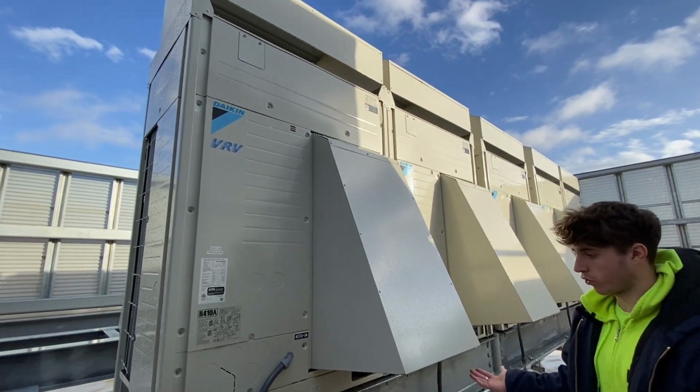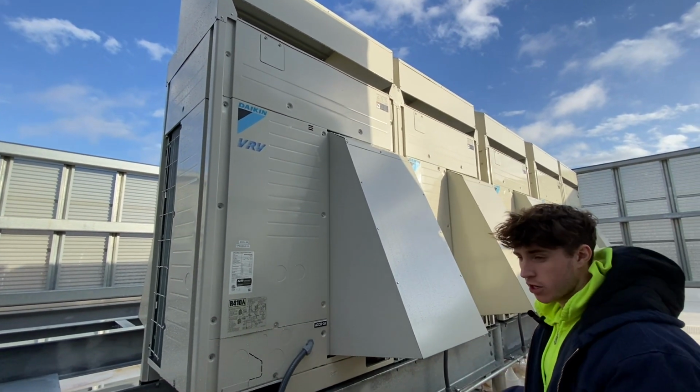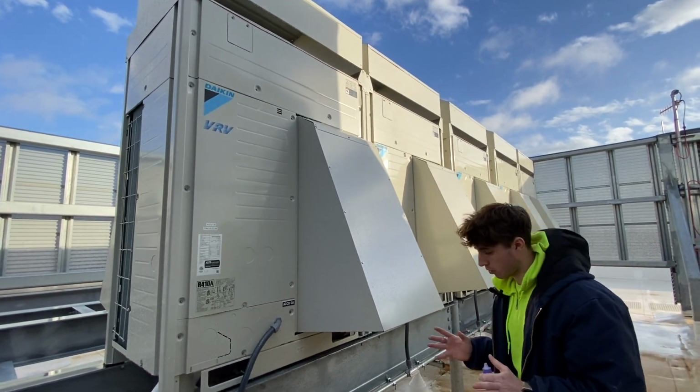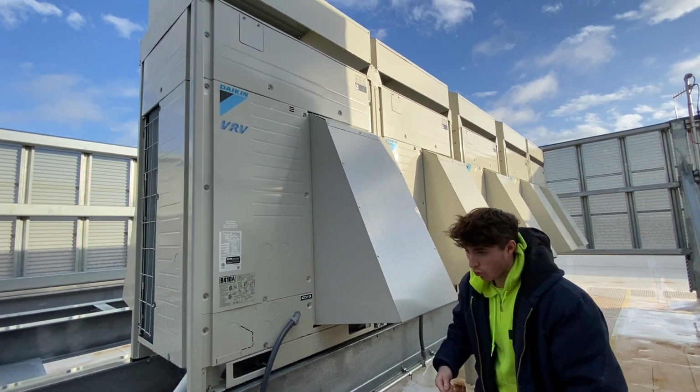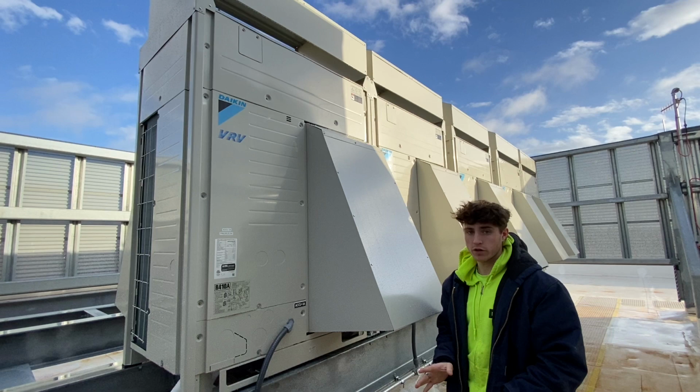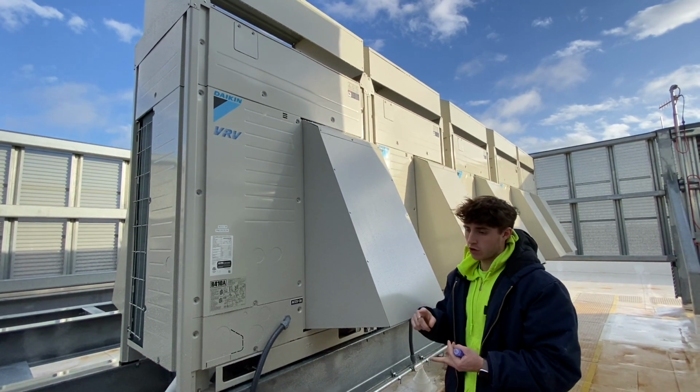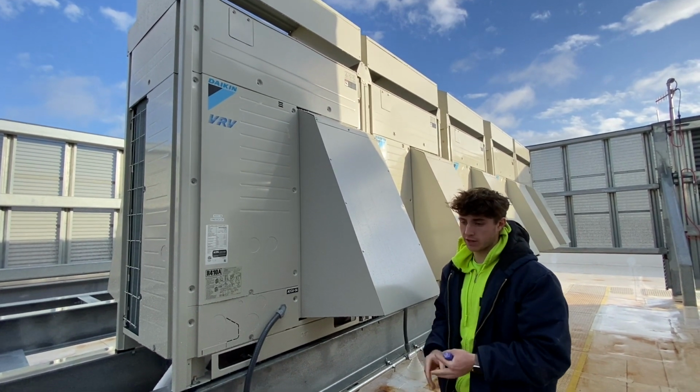It's going to go into these coils, but every year or so, you want to come up here, double check your coils, and give it one good wash just with water, nothing else. No coil cleaner, no soap, nothing like that, just water.